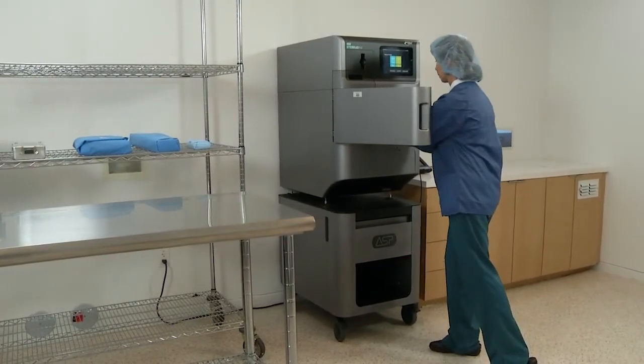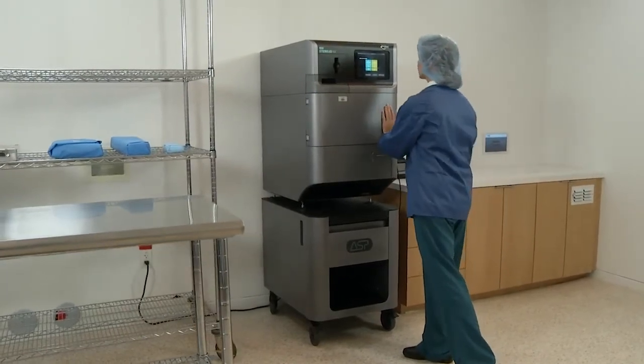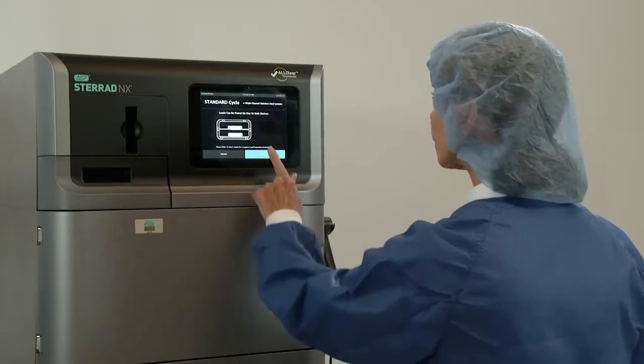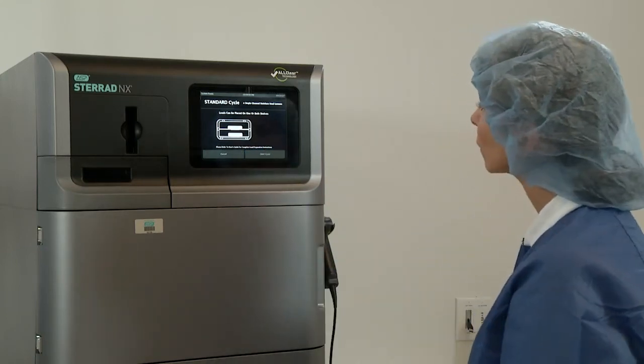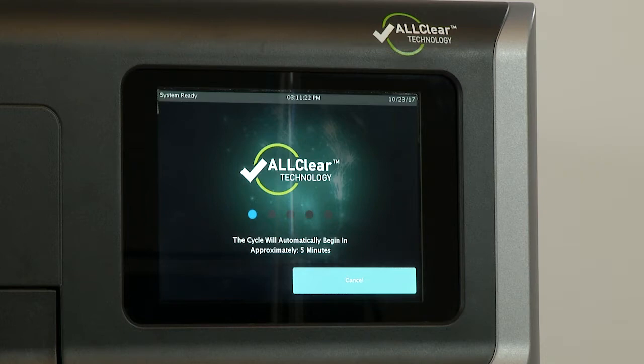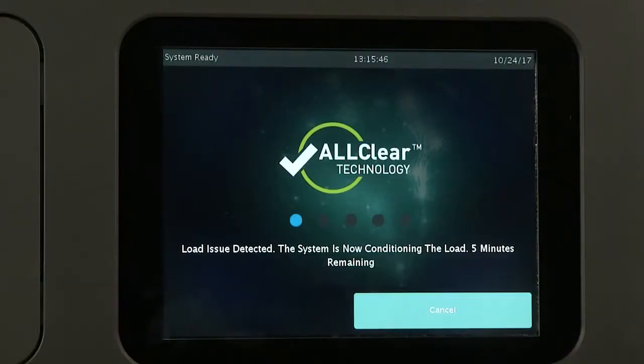Prior to beginning the cycle, the STERRAD NX sterilizer with all clear will run an automatic pre-cycle system diagnostics and load conditioning phase. The load conditioning process minimizes the number of sterilization cycle cancellations by detecting system problems and correcting load issues. This process completes in about 5 minutes and occurs prior to the start of the selected sterilization cycle. If a load issue is detected, the sterilizer will attempt to correct it. If all-clear technology cannot correct the issue, the selected sterilization cycle will not be started and a notification will be displayed on the screen. By utilizing the all-clear technology, problems with a load can be detected prior to the hydrogen peroxide being injected.